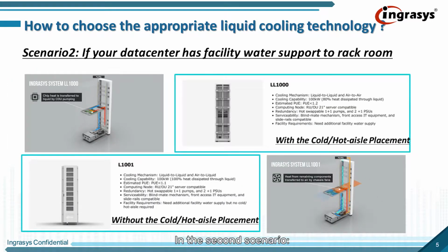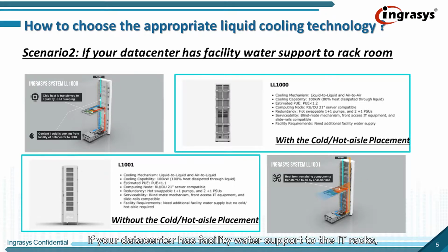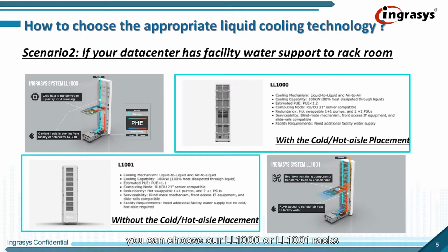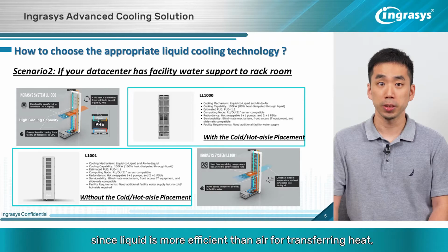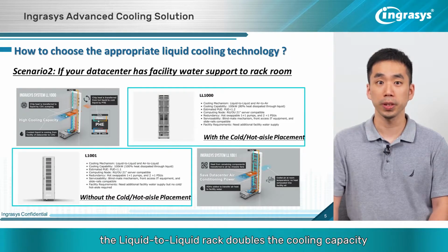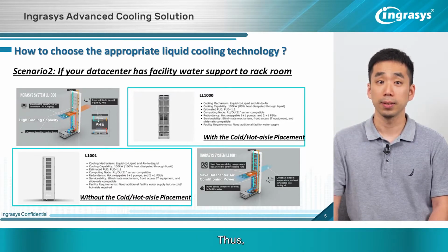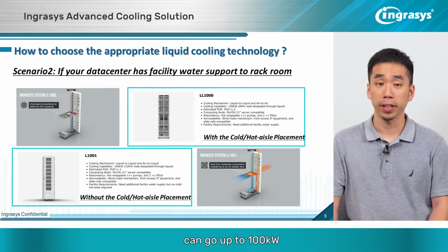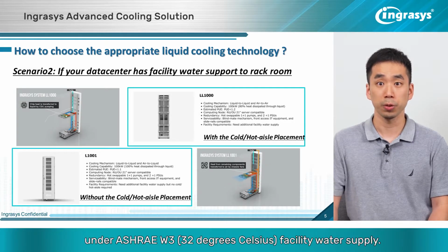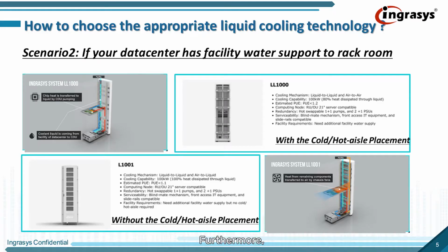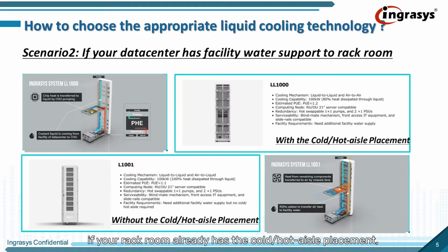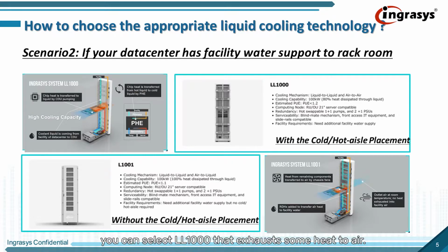As mentioned, this can provide you with a liquid cooling solution without changing your current data center infrastructure. In the second scenario, if your data center has facility water support to the IT racks, you can choose our liquid-to-liquid 1000 or liquid-to-liquid 1001 racks to fulfill your HPC requirements. As mentioned before, since liquid is more efficient than air for transferring heat, the liquid-to-liquid rack doubles the cooling capacity of the liquid-to-air rack. Thus, the cooling capacity of those racks can go up to 100 kW under ASHRAE W3 facility water supply. Furthermore, if your rack unit already has the cold and hot aisle placement, you can select liquid-to-liquid 1000 that exhausts some heat to air.